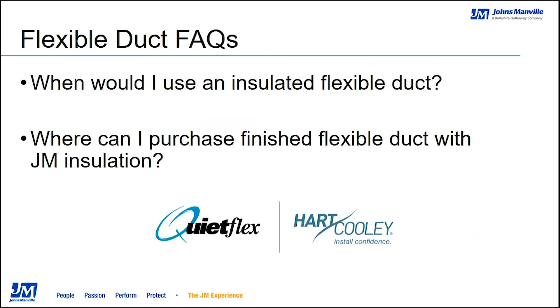The 2015 International Energy Code requirement for duct insulation is starting to require R12 insulation in climate zones 5 through 8. On this map, zones 5 through 8 are the green area stretching all the way up into northern Minnesota, and zone 8 is actually Alaska.